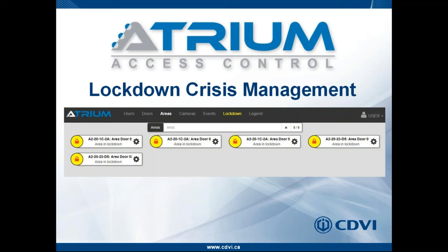When the lockdown is initiated or when the lockdown is stopped, I can trigger relays. For example, start lockdown, activate one of the relays on the A22. The relay is connected to an input module on a PA system, a public announcement system. When that relay is activated, the public announcement system will sense the change of condition and send a voice recording over the public announcement system to tell the people to find a secure area in the building or to evacuate the building if they can. So we can interact with external things.